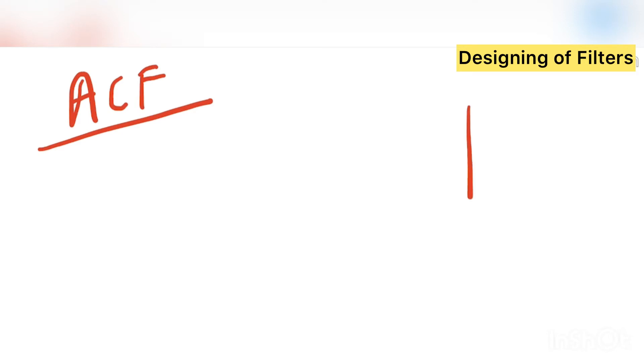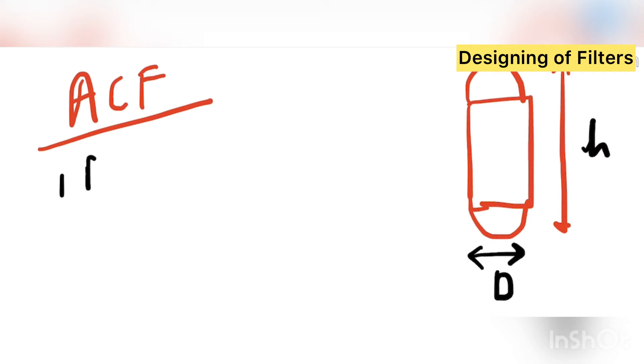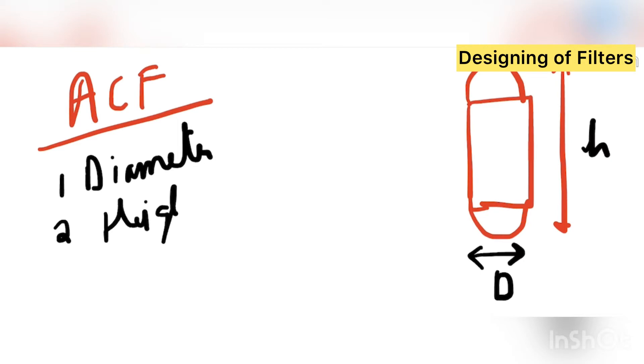Whereas this portion, this TSS and turbidity, this is removed by MGF and dual media filtration both. Now we see how to design ACF, that is the designing of activated carbon filter. So if I just give you a rough sketch, this is the filter. This is the shell, bottom shell, upper shell. So this is the total height and this is the diameter. So we want to know what is the diameter of filter and what is the height of filter.